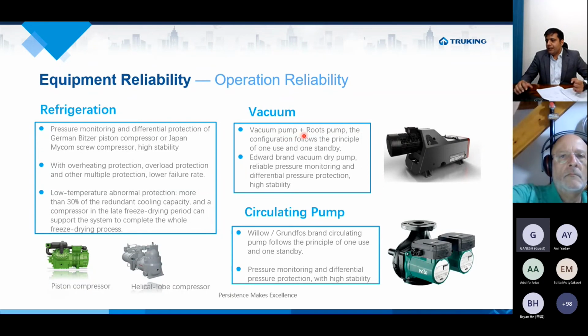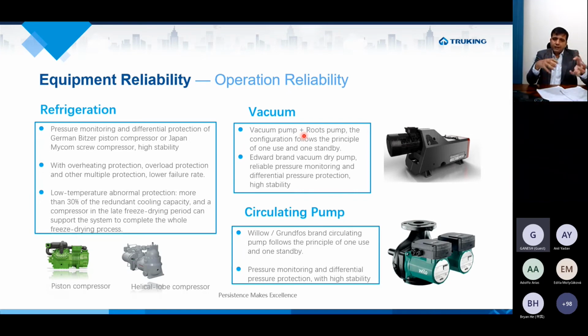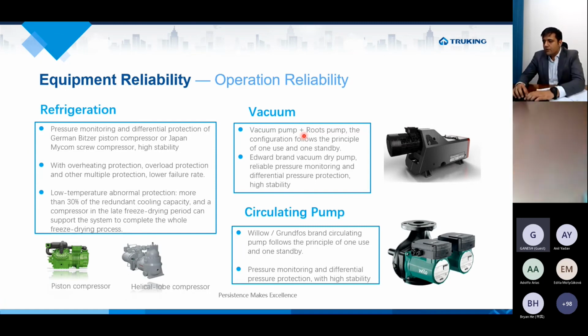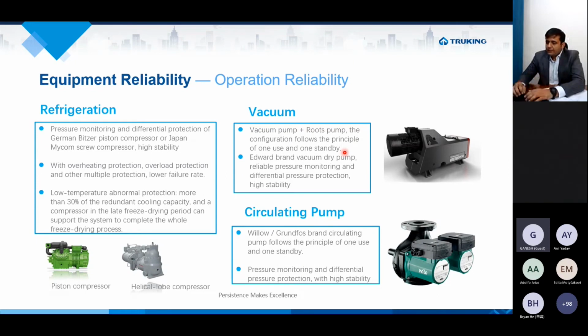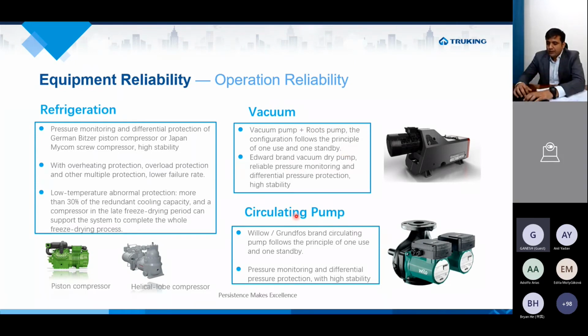Second, in the vacuum pumps, we have a vacuum pump, then we have a roots pump to create the vacuum. As I said before, we need to trap the ice in the condenser of the solvent. So that can again be one in use and one on standby, as a redundancy that can be employed in the whole system to ensure the equipment is reliable and you have more safety at your disposal once you are processing the medicine. The same goes for the circulating pumps, which can also have redundancy. As per standard, the design and model choosing of this equipment already consider over capacity for better usage.